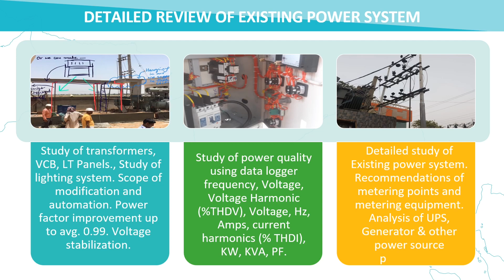Detailed review of existing power system: a report is provided with detailed review of the existing power system, in which we provide detailed study of the existing power system, recommendation of metering points and metering equipment, analysis of UPS, generator and other power sources, including study of power quality using data loggers, frequency, voltage harmonics, etc.